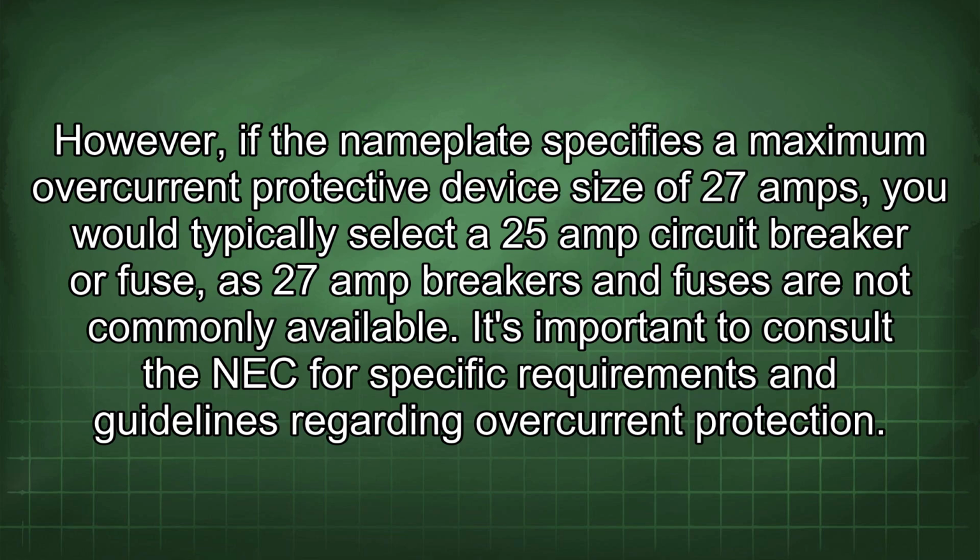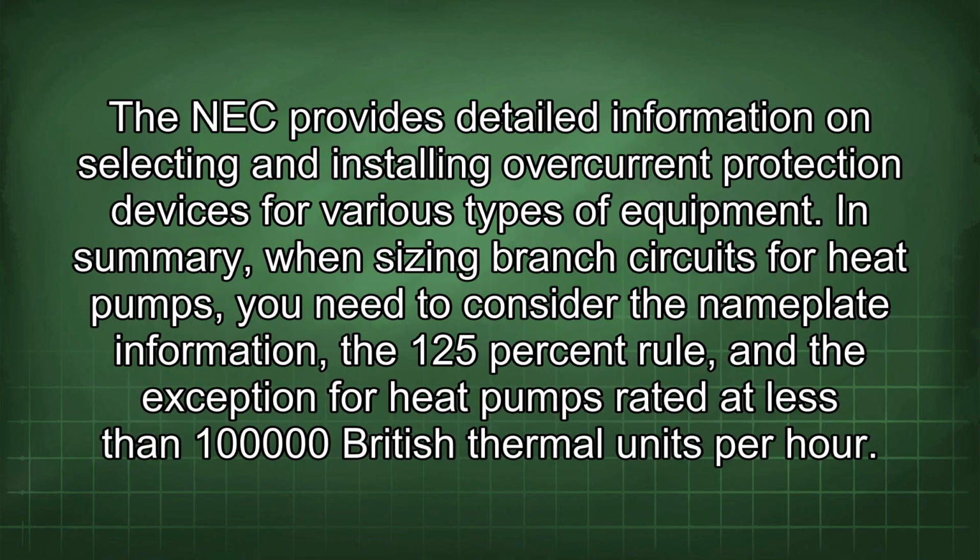It's important to consult the NEC for specific requirements and guidelines regarding overcurrent protection. The NEC provides detailed information on selecting and installing overcurrent protection devices for various types of equipment.